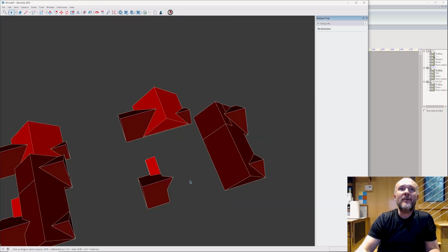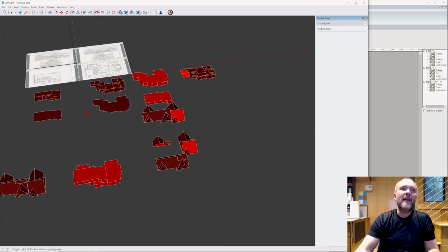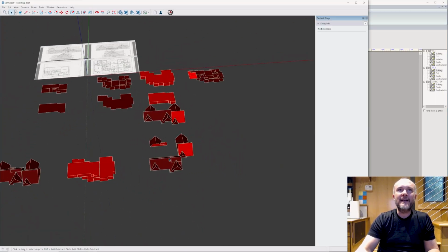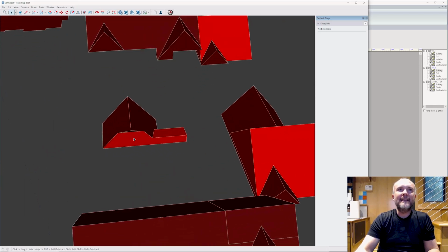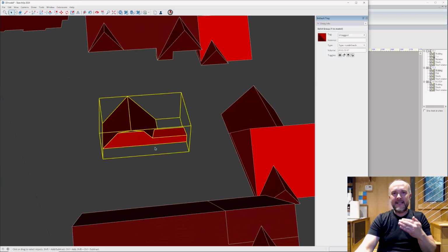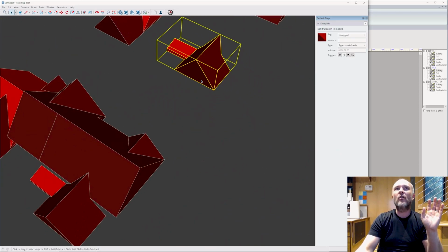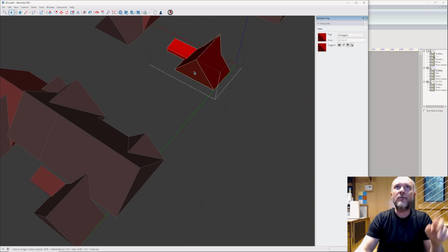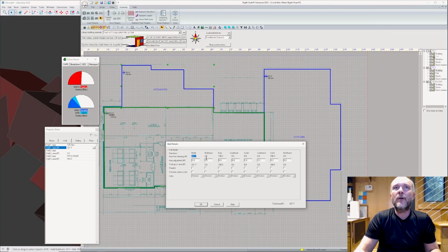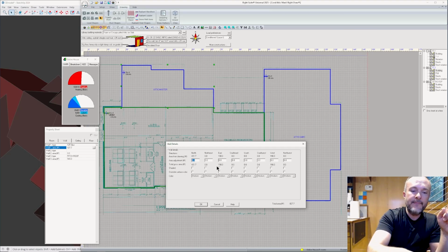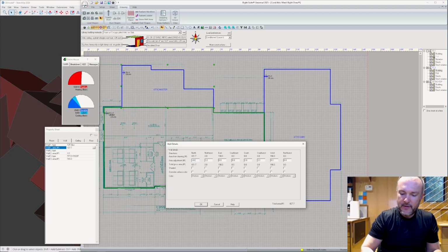So really, when I go in here, and again, just to clarify, south is down on this, right? So front door faces south. I don't have any south-facing wall. All of it is facing into the house. That's all what's called adiabatic, or there's no temperature difference, no delta T. On my north wall, I have 364.6. I'm going to call that 367 to the north. So I've got 431.7. So 367 minus 431.7 means I need to take out 64.7. And now I've got 367 in my total gross area.